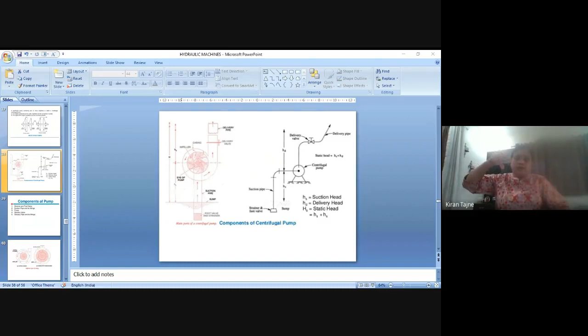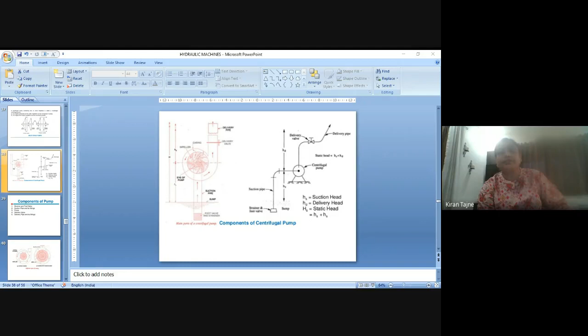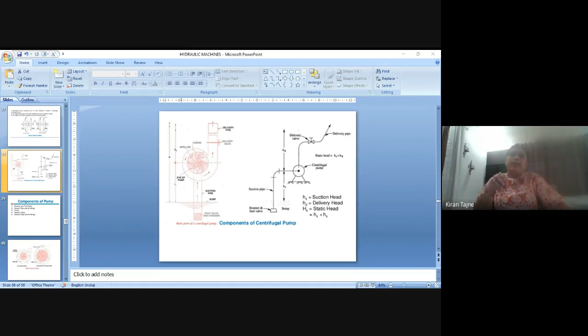So, initially the priming of the centrifugal pump should be done. What is priming? Priming is the process of filling the suction pipe, the casing of the pump, and then the delivery pipe up to the delivery valve with the liquid to be pumped. If priming is not done, the pump cannot deliver the liquid, because the head generated at the impeller will be in terms of meters of air, which will be very small.